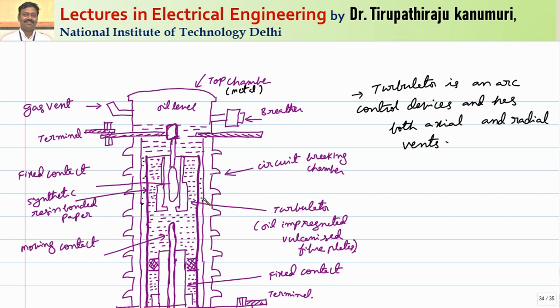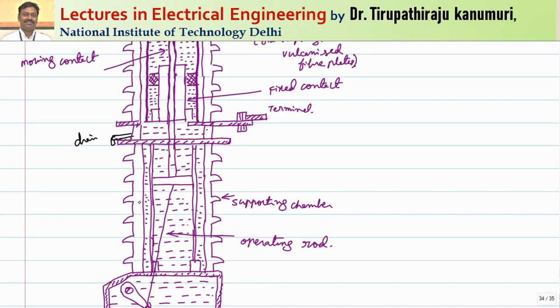The oil lies outside as well as inside this synthetic resin bonded paper cylinder. The outside oil provides the required insulation between the porcelain and the arc quenching chamber. Whatever carbon byproducts are produced during arc quenching remain only inside the inner chamber, so they do not severely contaminate the outside oil. This means the dielectric property of the outer oil — the insulation between the porcelain and this material — is not deteriorated at a faster rate.